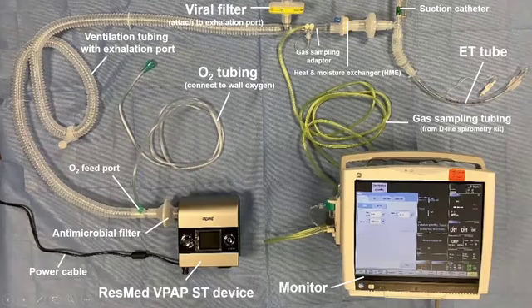Up here, there's a viral filter. Again, this is not a closed circuit, and one of the main concerns with patients with COVID pneumonia would be aerosolizing the virus and exposing healthcare workers. And so having that viral filter was a key piece. We placed a gas sampling adapter to be able to monitor the flow, the pressure, and the gases, the delivered oxygen, the end tidal CO2, with this monitor from GE. We placed a heat and moisture exchanger, HME, to allow for humidification, and ultimately this was attached to the endotracheal tube.